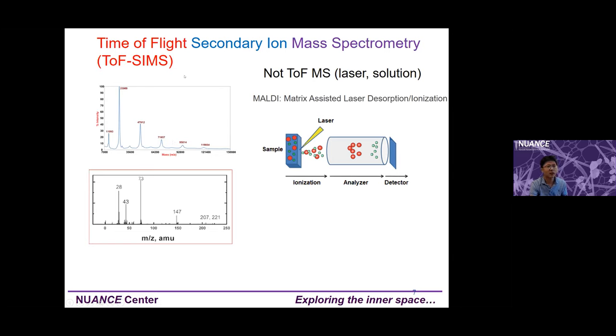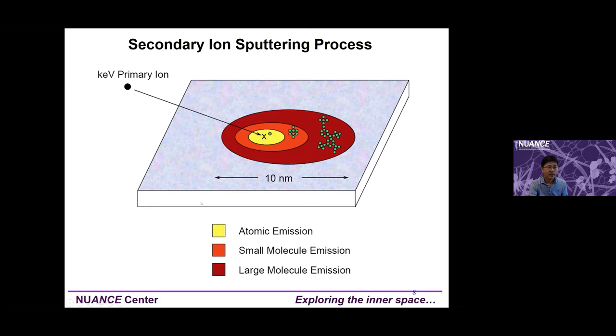MALDI-ToF is whole-material analysis; ToF-SIMS is just surface analysis. The next slide shows a schematic: when the primary ion strikes the sample, the center area mostly yields atomic or elemental ion information, and from the surrounding area you get small molecules. These are fragments. From the center, due to the strong energy, you get atoms. As you move outward and the damage is less, you can get larger intact fragments.